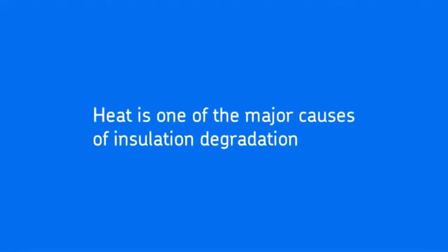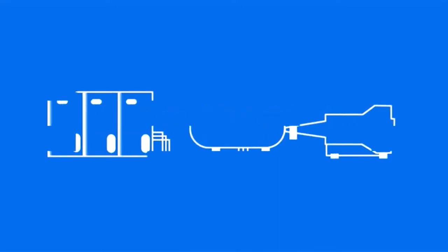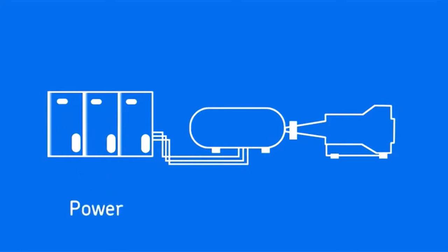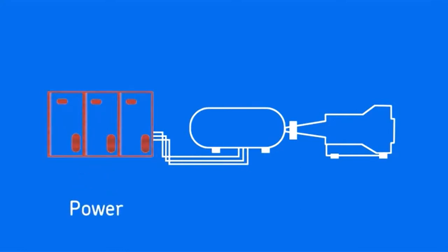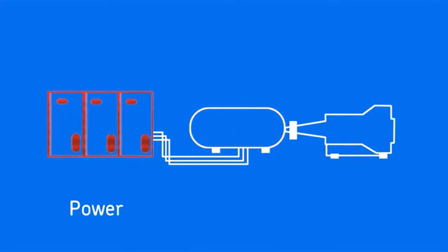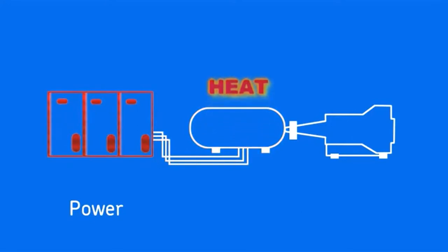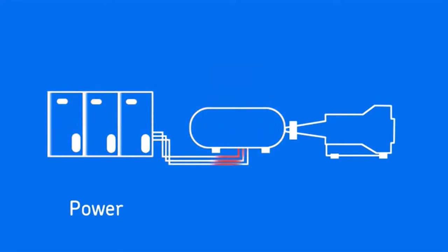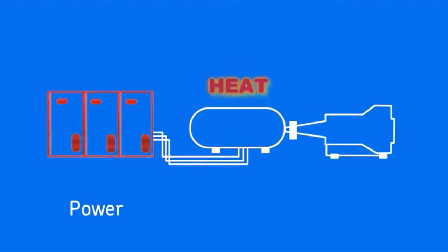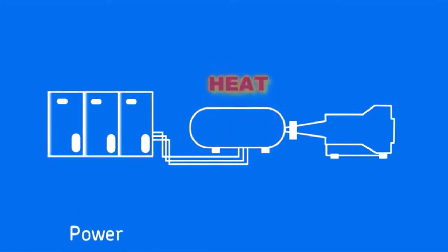One of the major causes of insulation degradation is heat. To understand more about what causes excess heat in the motor, let's look at the entire power, motor, load system. Electric machines are designed for good incoming power conditions. When power conditions deteriorate, excessive currents can flow in the machine, generating excess heat and shortening machine life. Incoming power tests look at voltage and current levels, distortion and balance.